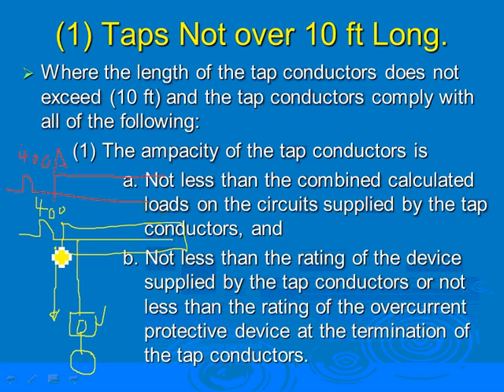So why is it so important, guys? Because they're cheap, 10 feet, and then I can tap another one from here, and a third one, and a fourth one. That's the most important application of that. And you keep tapping, right? What does tapping mean? You take phase A and you tap through it to a lug, with no overcurrent protection device. So that's your taps.